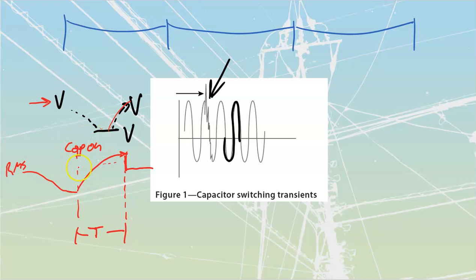The purpose of the cap is not to raise the voltage directly, it's to deal with the power factor. But dealing with the power factor does raise the voltage, so the regulator needs to switch over. This causes an overvoltage that can last a couple of minutes at most before the transformer regulators change that setting.